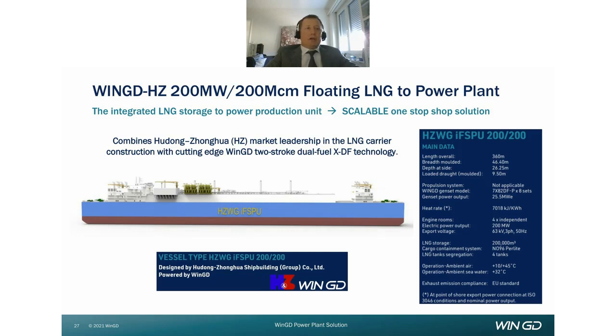The unit shown here is the first of its kind to produce 200 megawatts and store 200,000 cubic meters of LNG to ensure about 4 months of autonomy at 85% of the rated power without any LNG resupply.